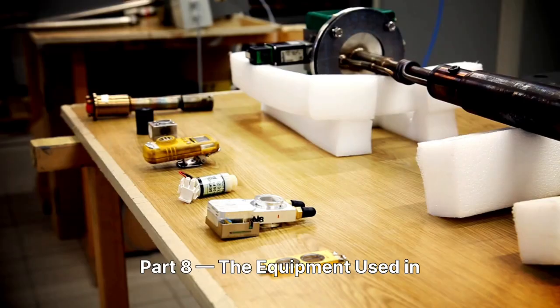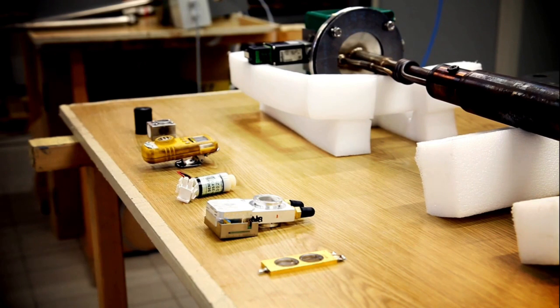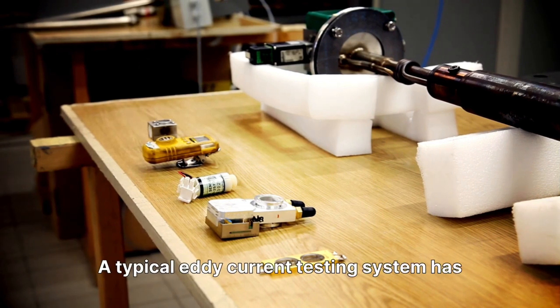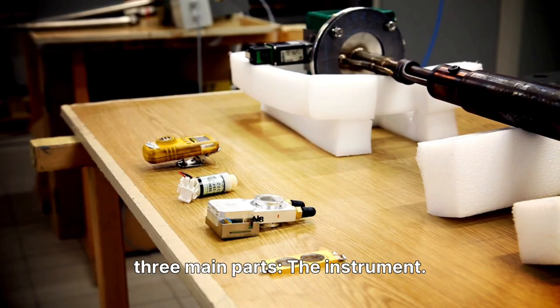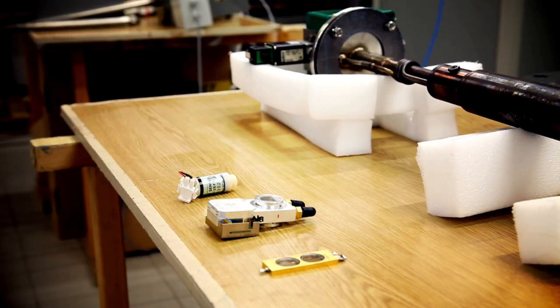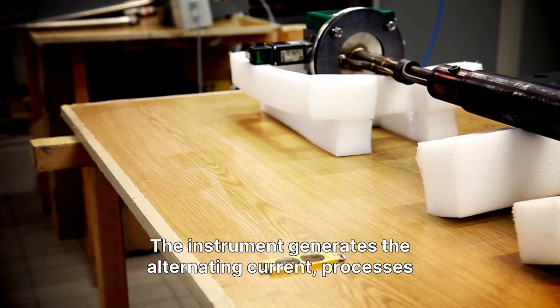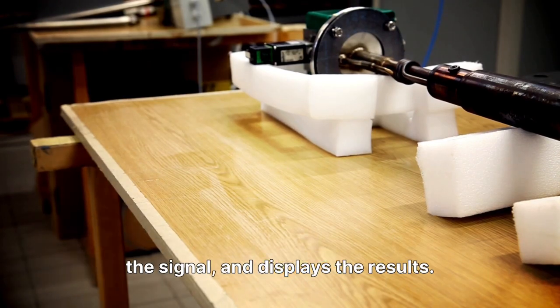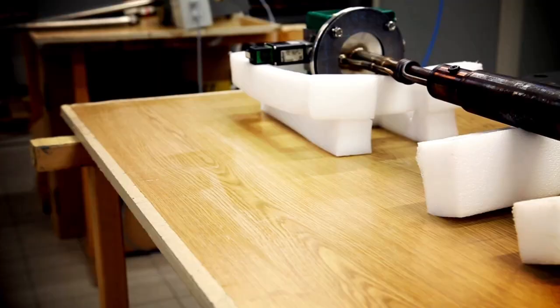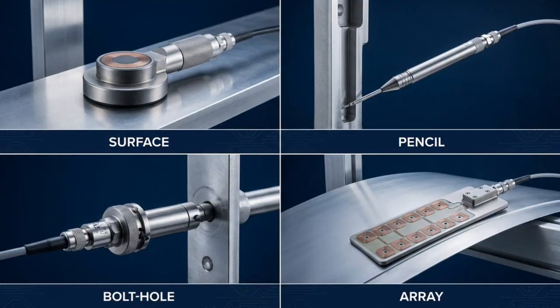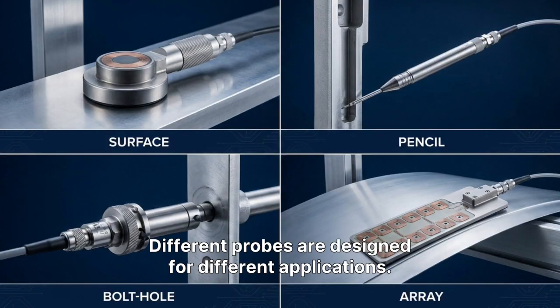Part 8. The equipment used in eddy current testing. A typical eddy current testing system has three main parts: the instrument, the probe, and the calibration standard. The instrument generates the alternating current, processes the signal, and displays the results. The probe contains one or more coils. Different probes are designed for different applications.